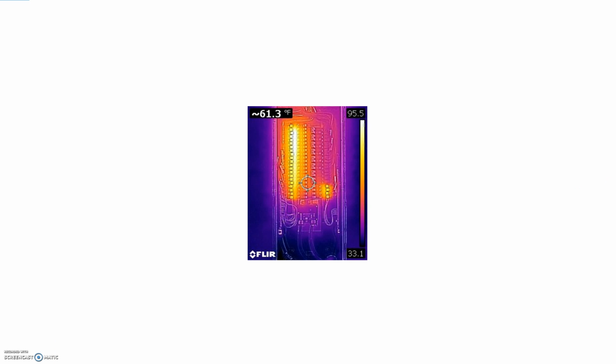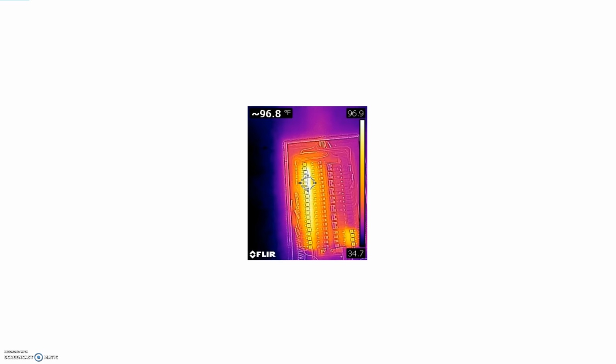Infrared images of the electrical panel. You can see the warm areas are the arc fault breakers. They have circuitry inside them that generates some heat, but none of them were close to 140 degrees. So it's fine. This is typical warming for arc fault breakers.